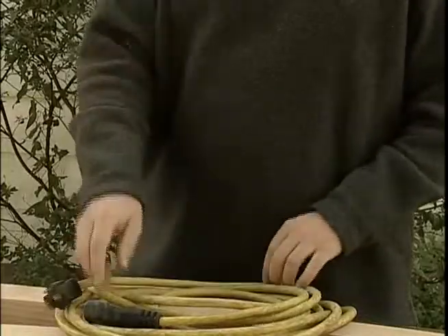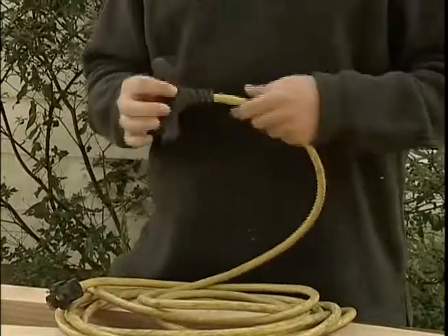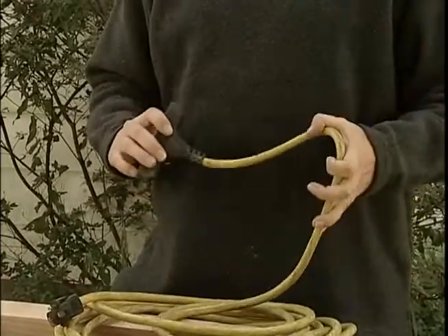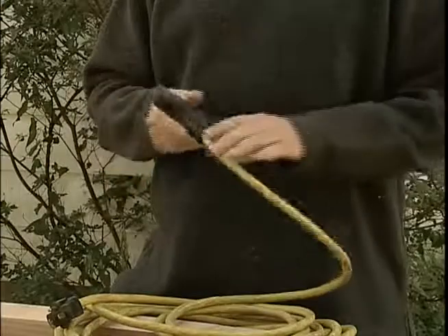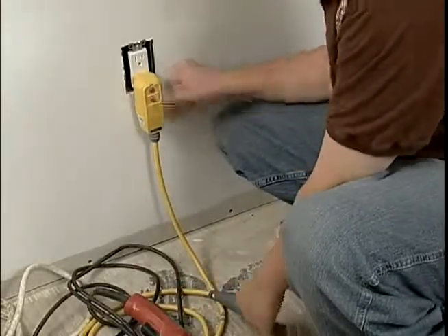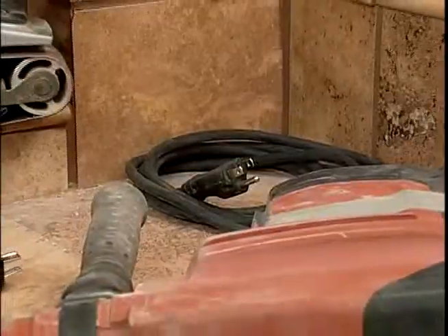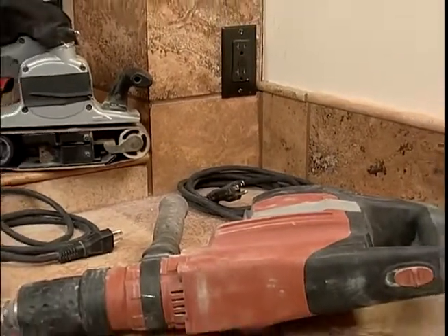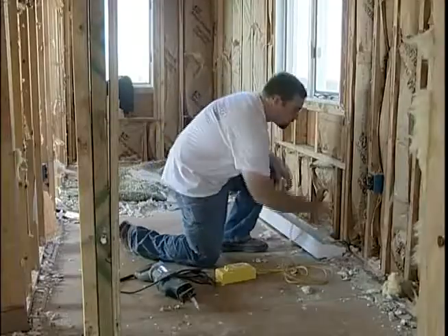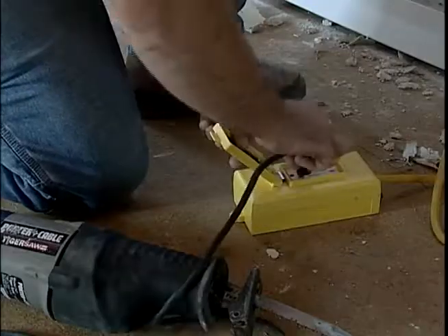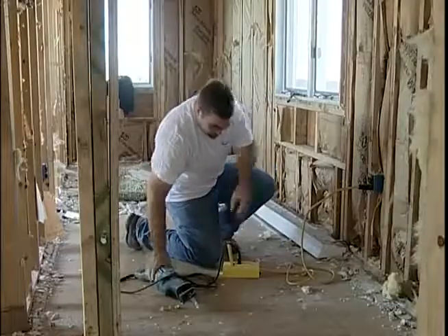It must cover all receptacles which are not part of the structure that is being erected, equipment that is connected to electrical power by cords and plugs, as well as the electrical cords themselves. Receptacles on the ends of the extension cords must also be protected by GFCIs. In this way, either all of the sources of electricity on the construction site will be grounded, or if the sources aren't grounded, all of the tools and equipment that are plugged into the ungrounded sources will themselves be grounded.